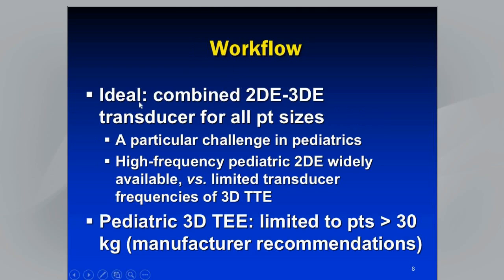The next thing we're going to talk about is workflow. What we would like to ideally use is a combined 2D and 3D transducer. Not that we just have one transducer for all patient sizes, but for any patient size, we should be able to switch between 2D and 3D echo imaging without any difference in the quality of the image. This turns out to be a particular challenge in pediatrics because high-frequency pediatric 2D echo transducers are widely available, whereas the 3D transthoracic transducer that's available for pediatric usage has limited transducer frequencies. As a result, we are somewhat constrained in our ability to obtain super high quality images with 3D transthoracic echo, especially in little babies.